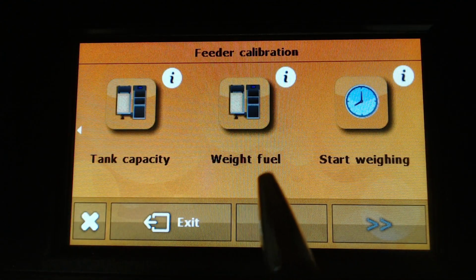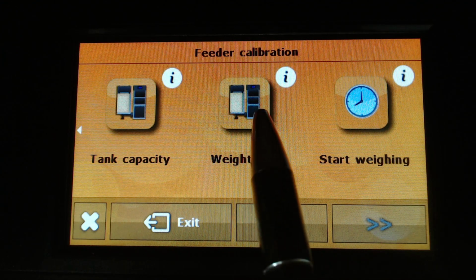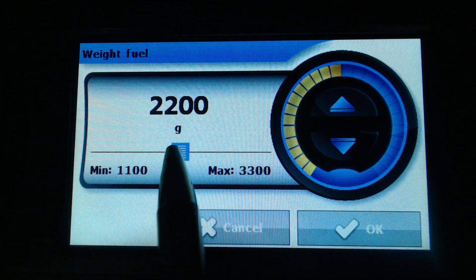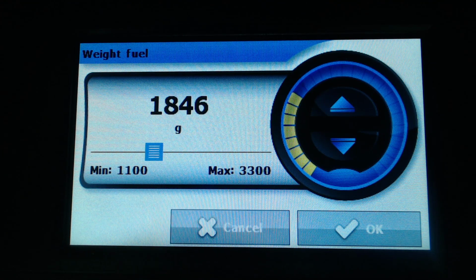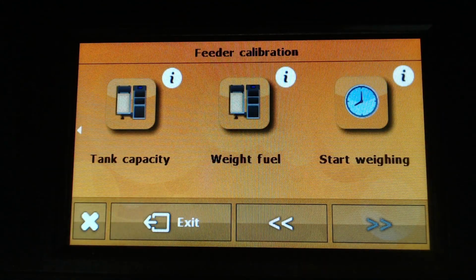When you know the weight of the pellet, you go here to the weight fuel function and input the weight of the pellet you measured. You hit OK, and then your control unit knows how fast, or how many pellets, your feeder is able to supply in 5 minutes of time, and from that the control unit is able to calibrate the feeder for the power you selected.